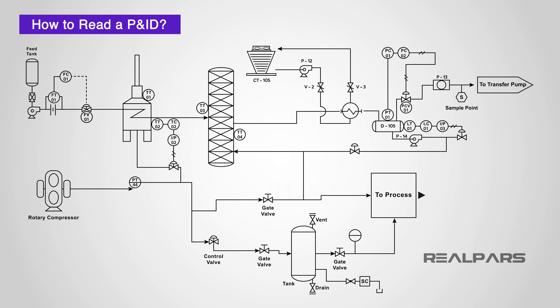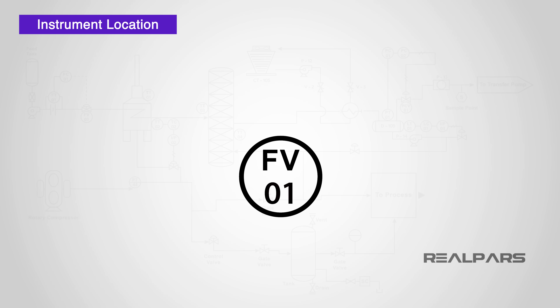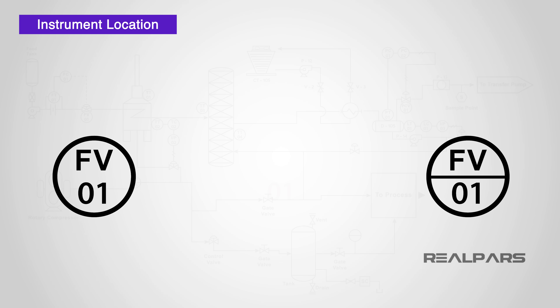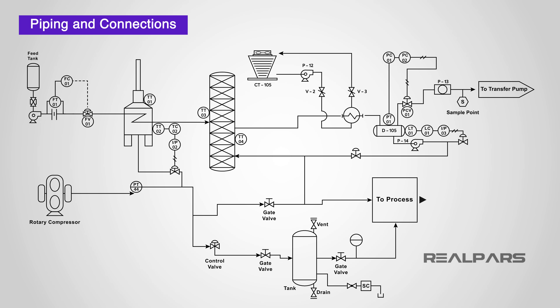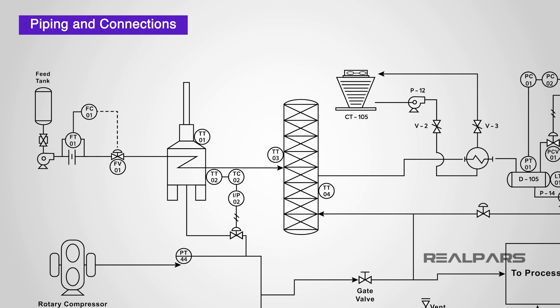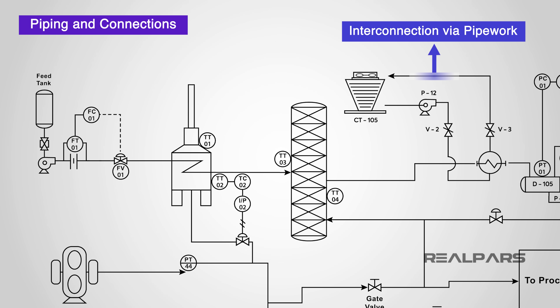Symbols, circles, and lines are used to represent instruments and to show how they are connected to the rest of the system. For our device FV01, represented by a circle, we can also tell from the P&ID where the instrument is located. The presence or absence of a line in the circle determines the location of the physical device. The piping or connection lines also tell us about the instrument — a solid line indicates the connection is via pipework, whereas a dotted line indicates an electrical connection. It is worth familiarizing yourself with the different types of connection symbols, as this can give you an insight into the function of an instrument even before you know its code.